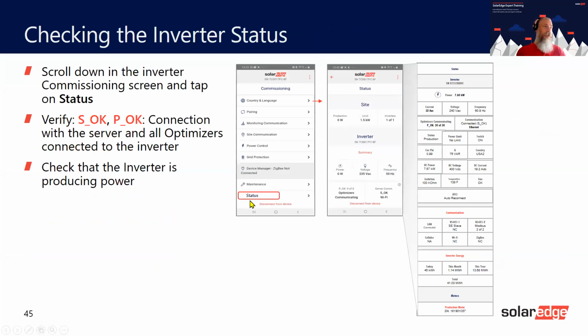Status. You click on status and you get an overall picture, and you just basically scroll the phone up and you get all the information about the inverters, what they're doing. This is arc circuit interruptions showing auto reconnect here. You've got SOK, which means you've got communication. You've got 30 of 30 optimizers. What else have we got? Energy this month. You've got the information about the meters. So it's all on here. Literally, you can just scroll up. And don't forget that the beauty of it is you can take screenshots to prove that you have SOK, to prove that you've got everything set up correctly.